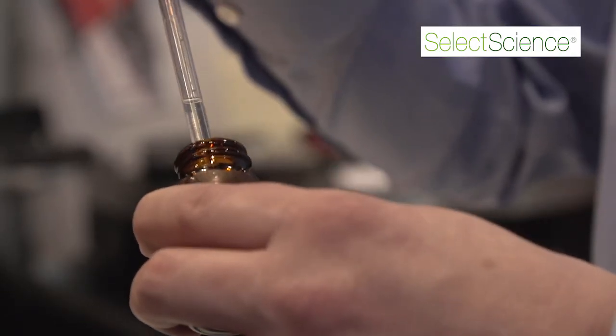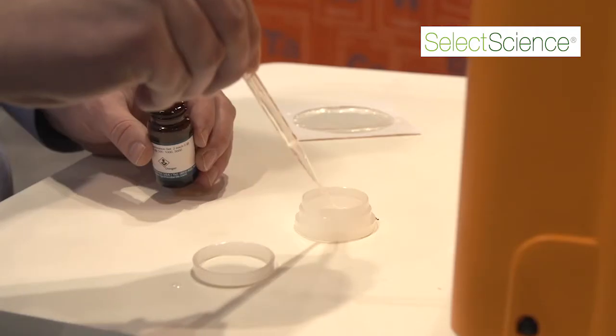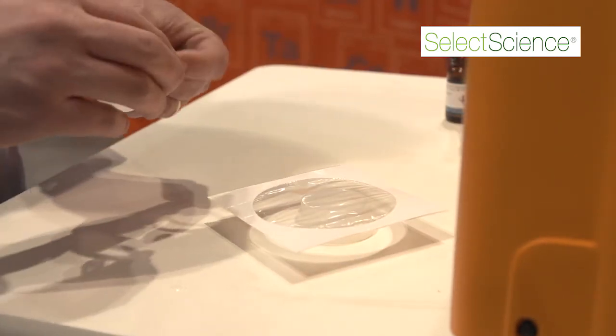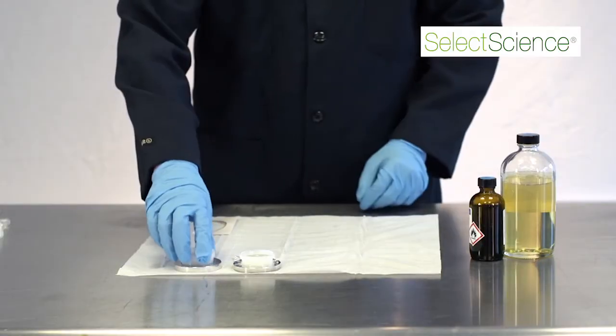The SINDIE Plus Chlorine enables you to use a direct analysis technology. You simply put the sample into the cup, put a film on it, place it in the instrument, and press measure — within a few minutes you have both your total sulfur and total chlorine measurement. You don't have to spend any time reconfiguring the instrument, whether that's changing the detector or changing sample introduction techniques. It can measure both light hydrocarbons and heavy hydrocarbons without any of those changes.